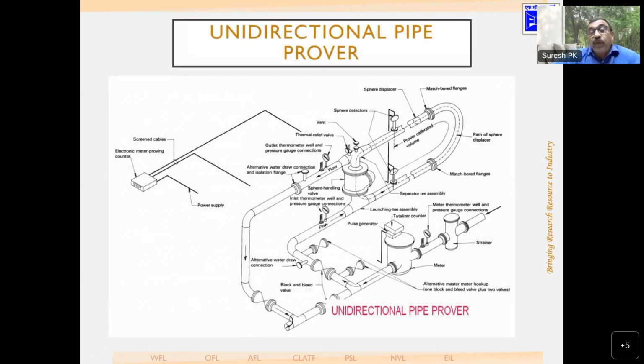If you see, there are different kinds of provers. One is the unidirectional prover, in which the flow comes from only one direction from the meter. It passes through the calibrated length, pushing normally a ball or something, and the calibrated prover volume is this much. The flow comes through the meter, then through the prover. It moves from here to here and then moves back to the main system after calibration. The ball moving across this will fall here and then go back to its original position when you take the next run.